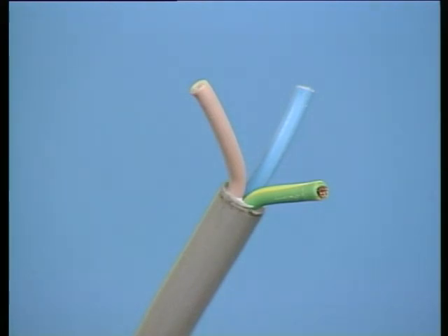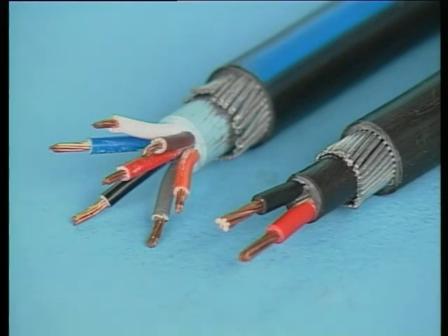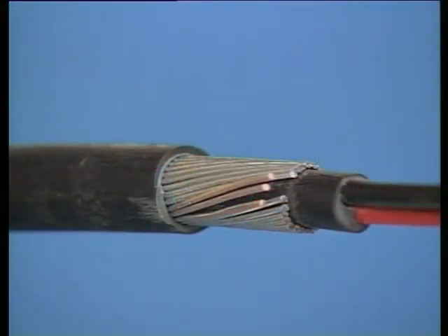Cabtyre illustrates the typical construction of a simple multi-core cable. 3 individual conductor cores are each insulated with color-coded PVC material. The 3 cores are encased with a bedding material which may also be PVC or even silicone rubber. More complex low-voltage cable designs include house supply types, used where permanent supplies are installed. Such cable types are usually of the earth continuity conductor or ECC design, which we will see again later in this program.